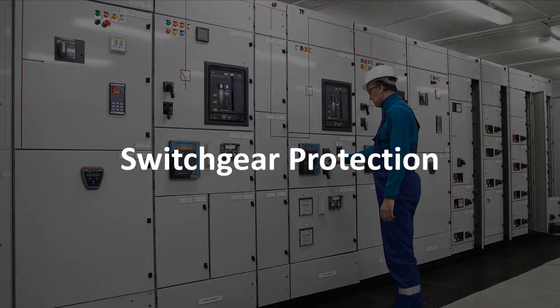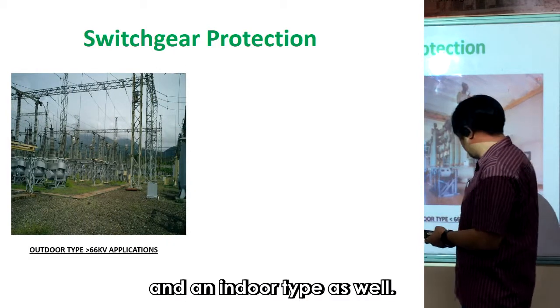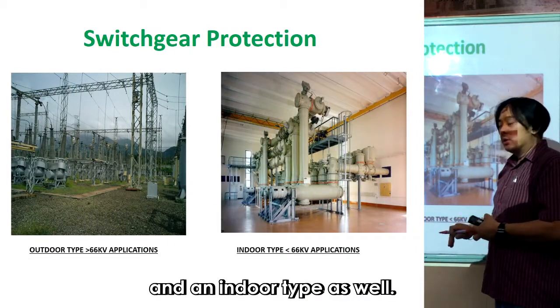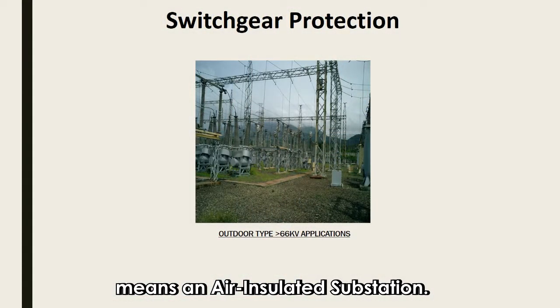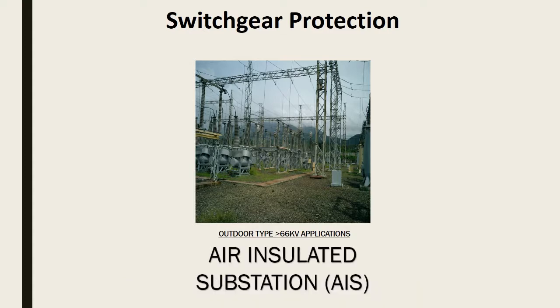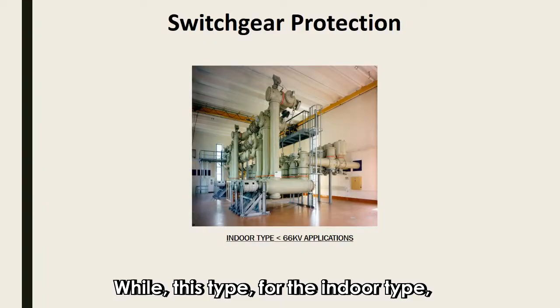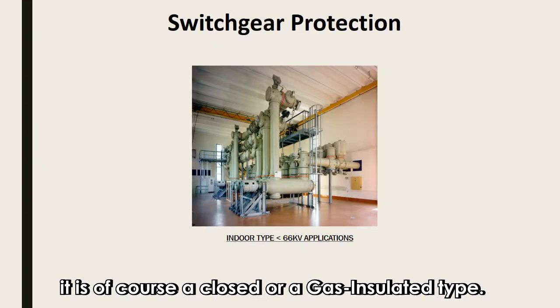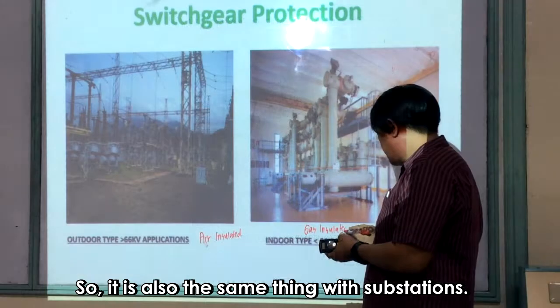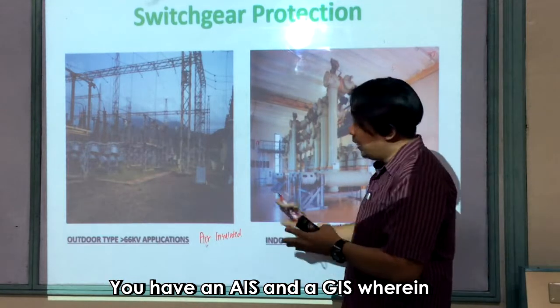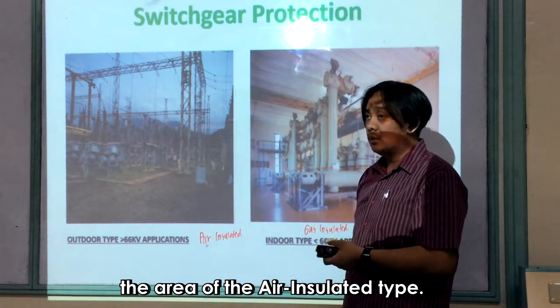As we have discussed, a switchgear can be an outdoor type and an indoor type. It is similar to a substation: an outdoor type means an air-insulated substation (AIS), while the indoor type is a closed or gas-insulated type (GIS). GIS occupies about one-fifth the area of the air-insulated type.